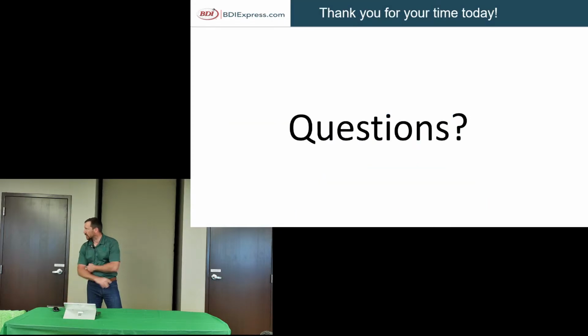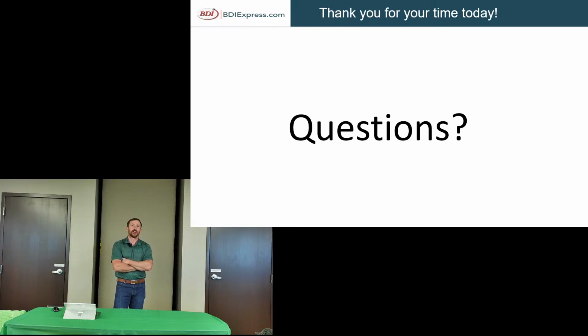But basically, what I like to do, like your question that you had, is we like to get out with you guys and solve problems. So if you have problems with bearings, or want us to look at applications with the drive design, we can do that for you guys. We put labels on air handling units to make it easier for you guys. When you go back to look at an air handling unit, you have it broken down with what sheaves are on there, what bushings, motor horsepower, belts that were used, all that information.